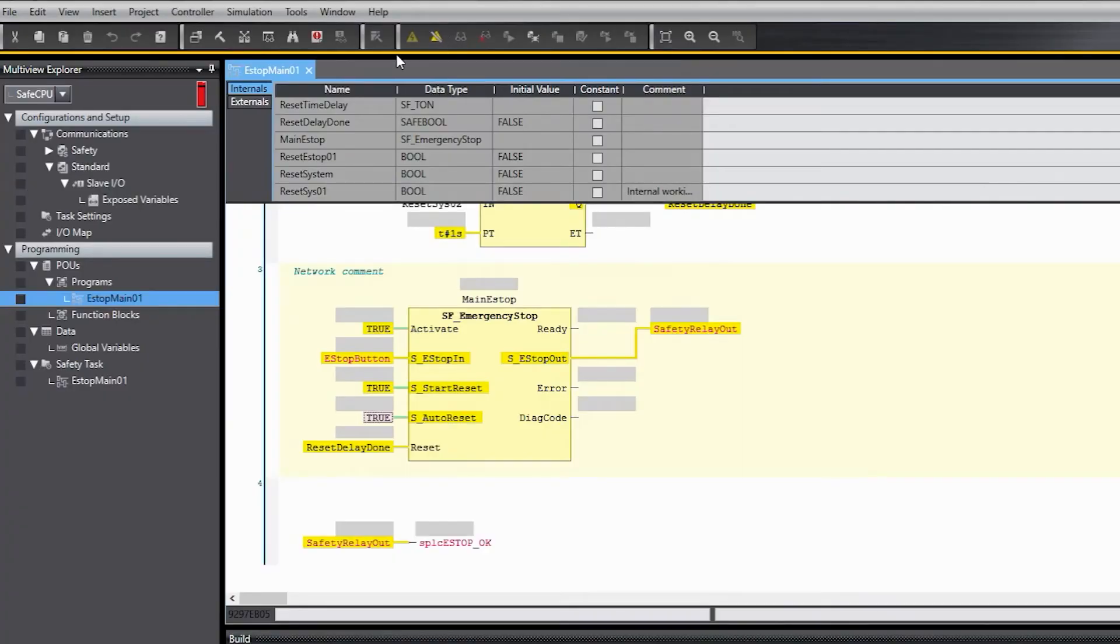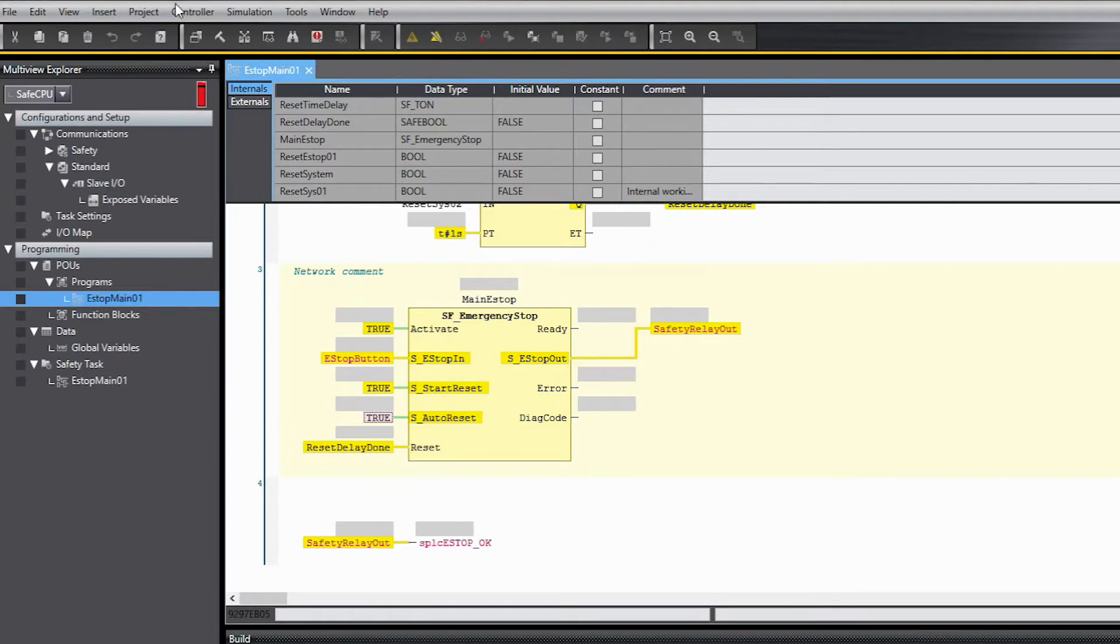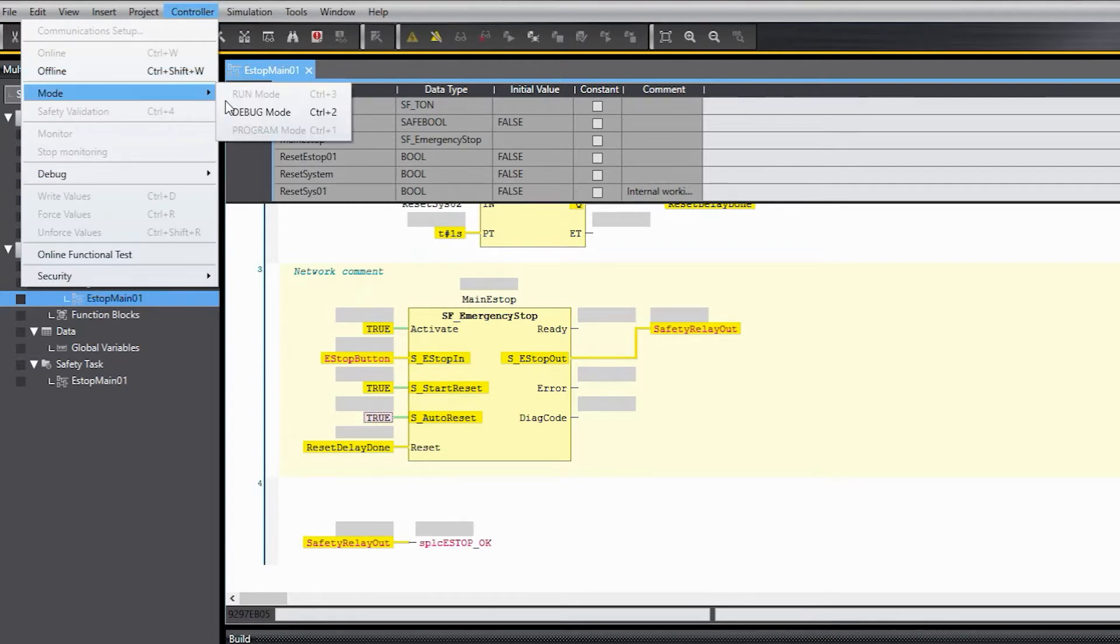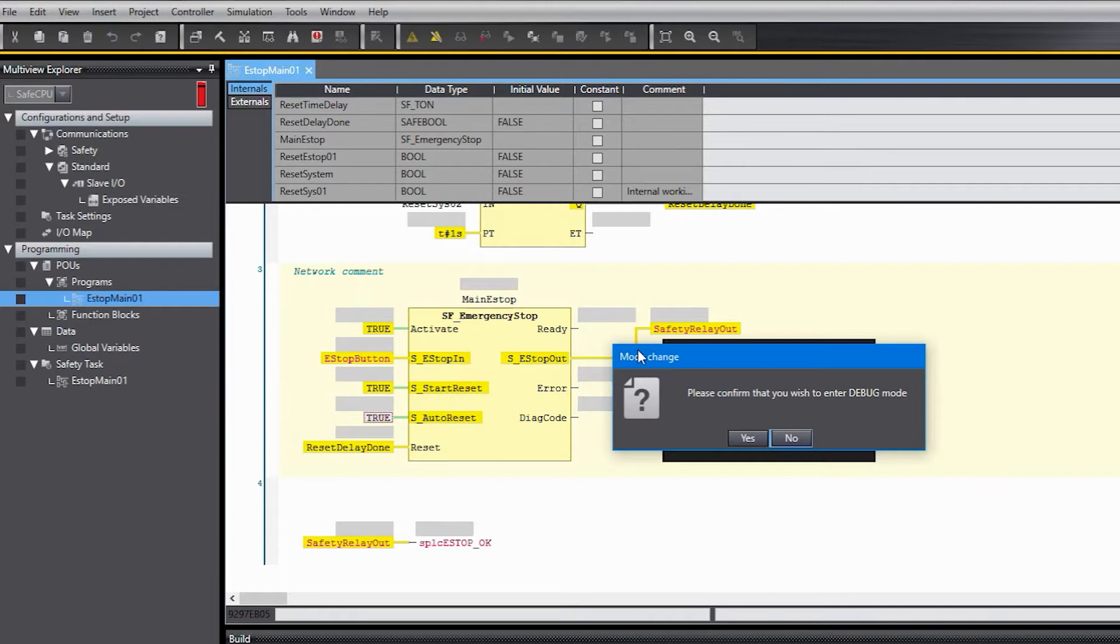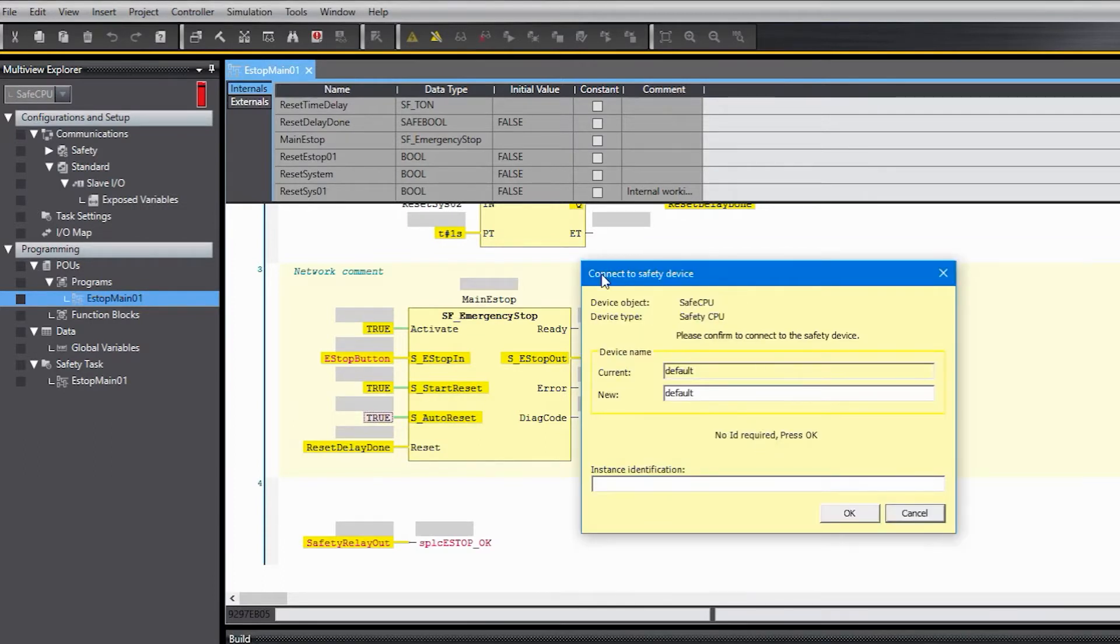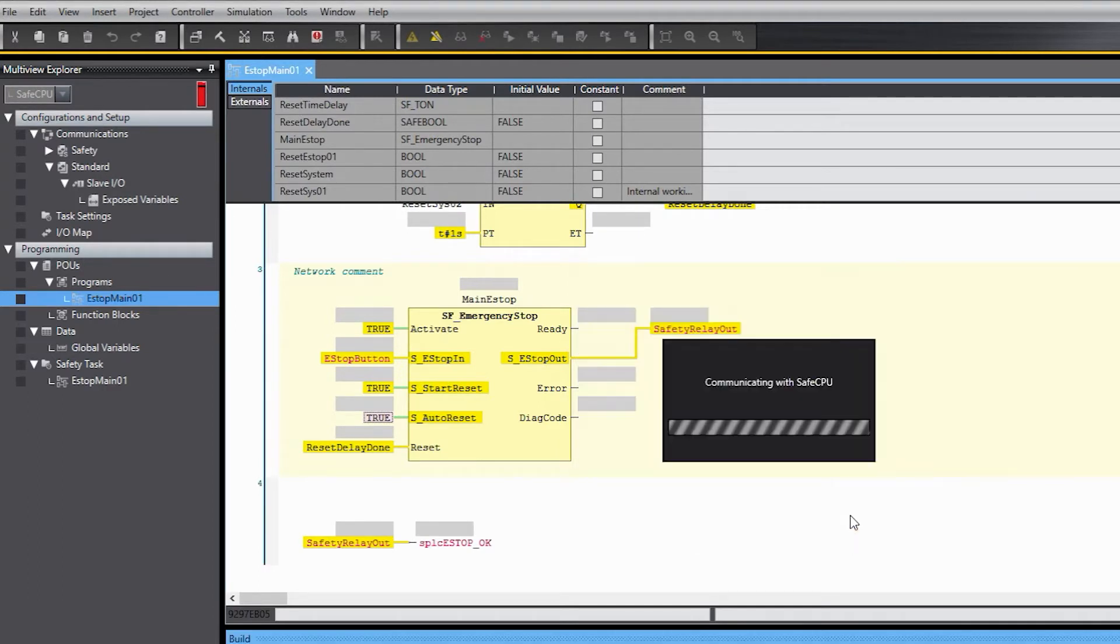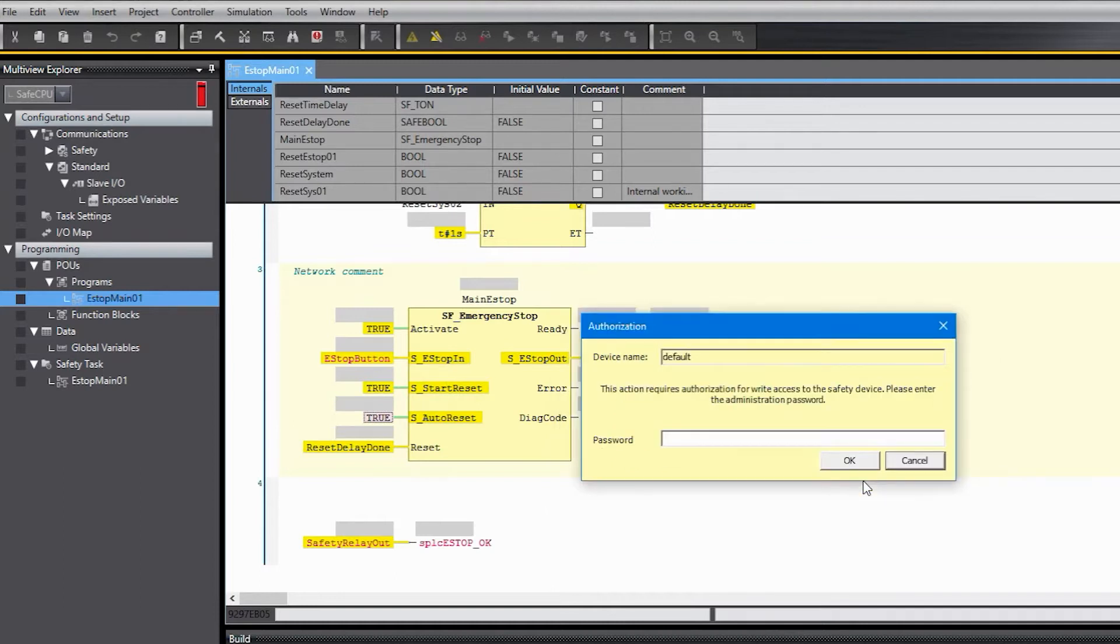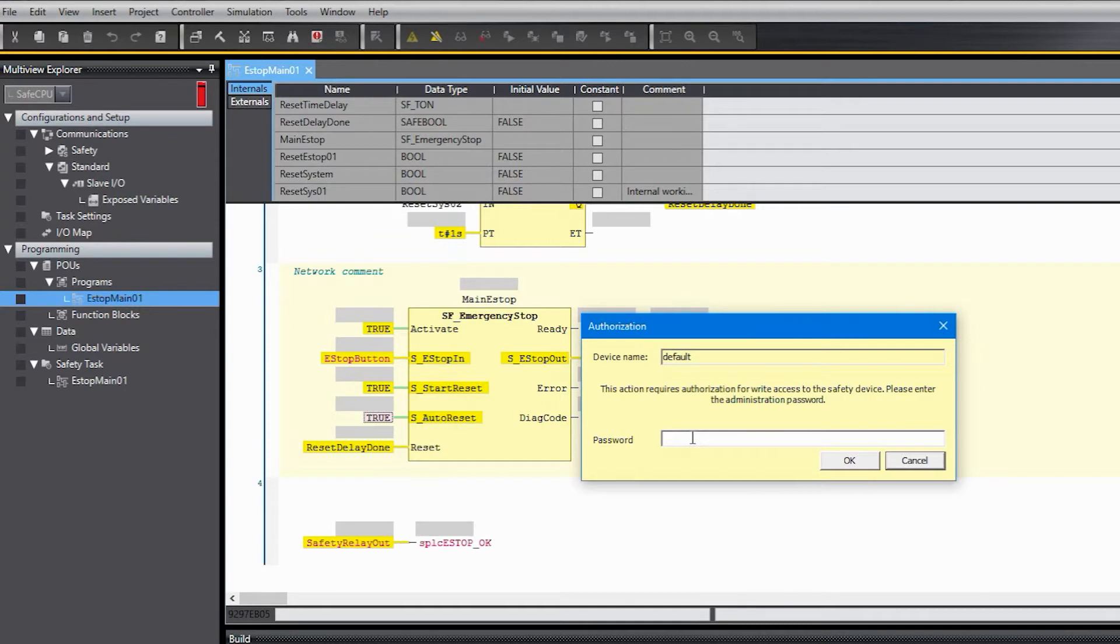So I'm already online, you can tell by this orange bar here. I clicked on this online button here and now that I'm online I need to go to the controller menu and change the mode to debug. You'll get a bunch of these messages that you can just answer yes or okay to. If you have entered a password for the controller to protect it, then you need to enter that here. It's a good idea during development just to leave the password blank until you actually deploy the system out in the field or sell the machine that it's on.